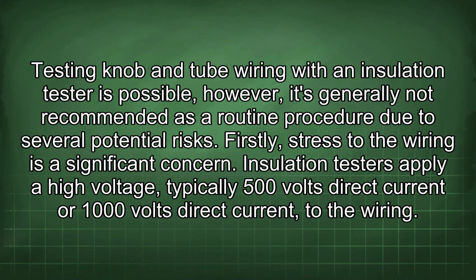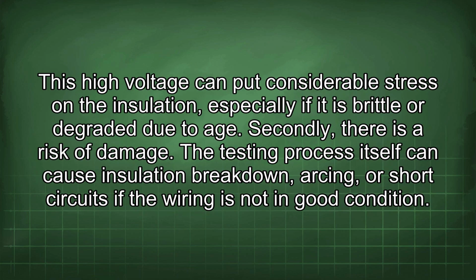Testing knob and tube wiring with an insulation tester is possible, however, it is generally not recommended as a routine procedure due to several potential risks. Firstly, stress to the wiring is a significant concern. Insulation testers apply a high voltage, typically 500 volts direct current or 1000 volts direct current, to the wiring. This high voltage can put considerable stress on the insulation, especially if it is brittle or degraded due to age.